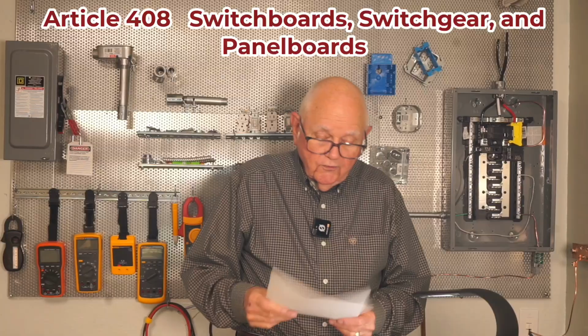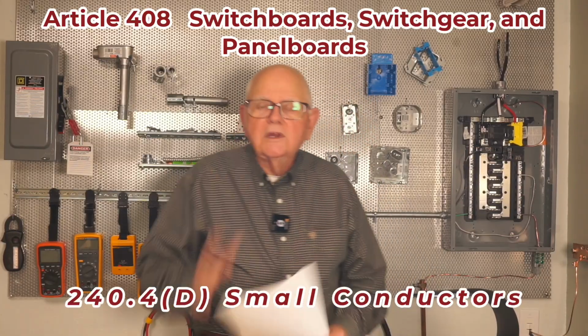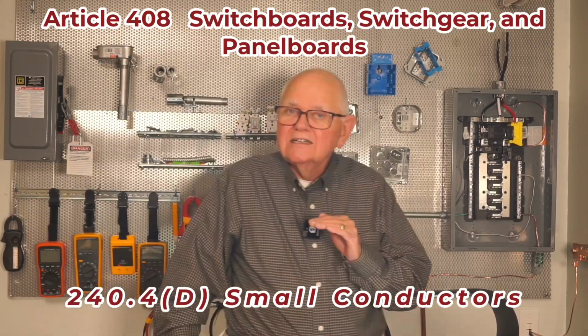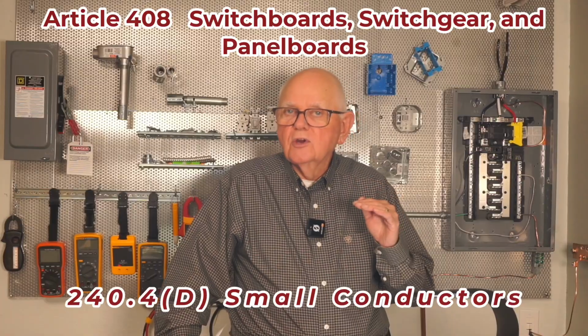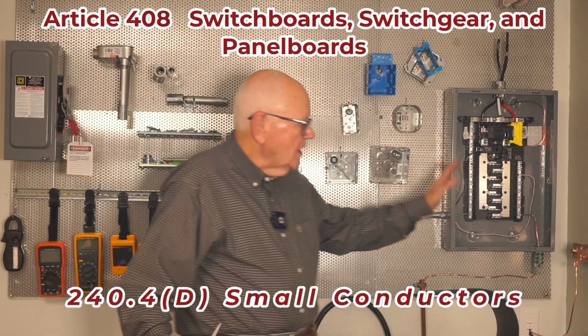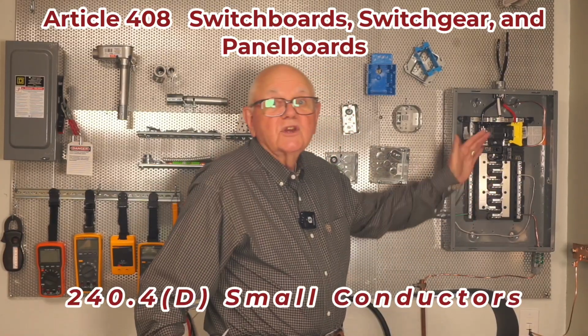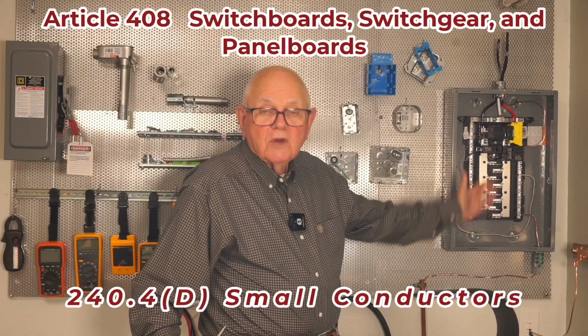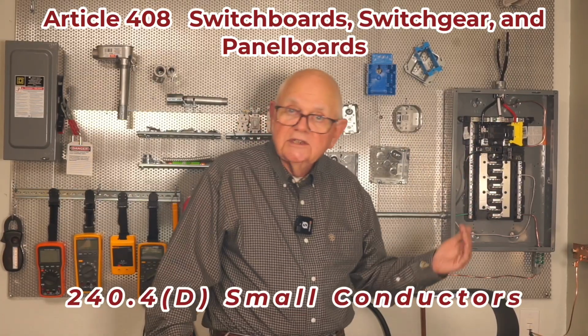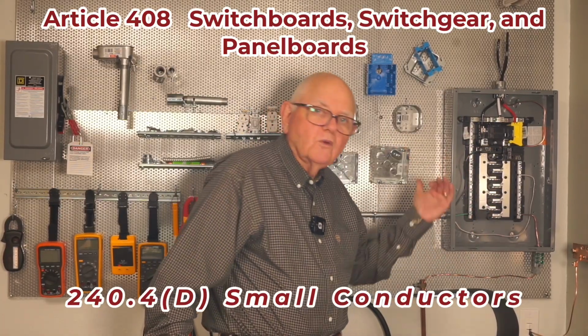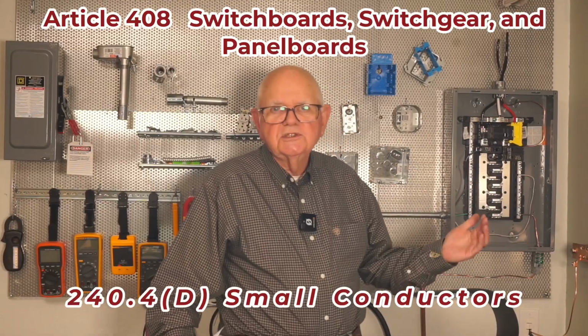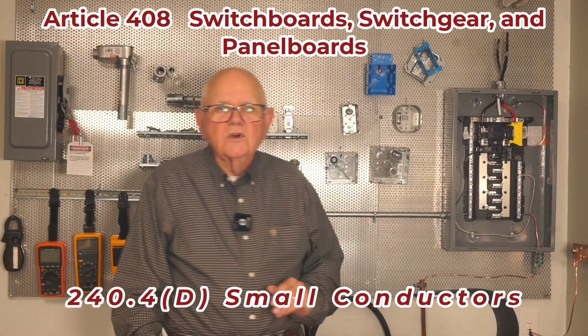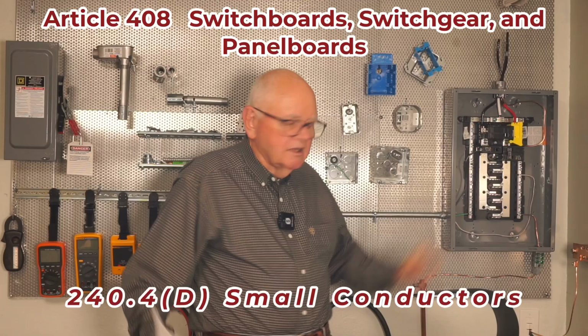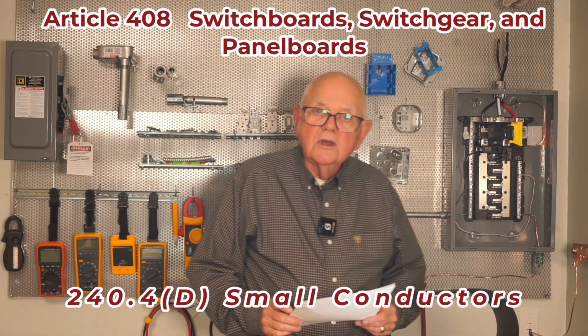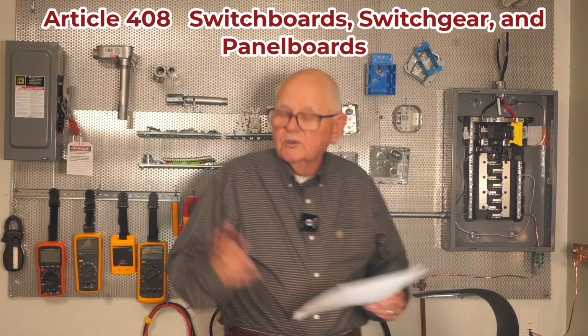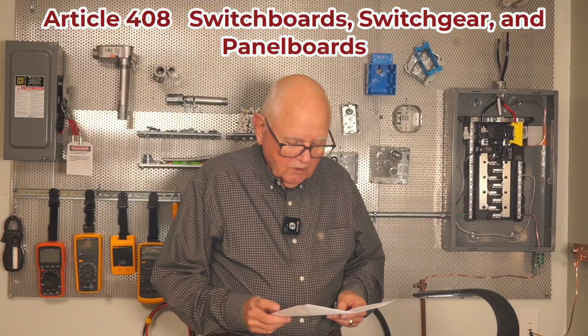Oh, 240.4(D) is another important one. Article 240 is on overcurrent protection. So 240.4(D) talks about, for instance, on a 15 amp breaker, what am I going to use? 14 AWG wire. What am I going to use on a 20 amp breaker? 12 AWG and so forth. So take a look at 240.4(D) if you get involved in installation of overcurrent protective devices, fuses, or circuit breakers inside of panel boards.